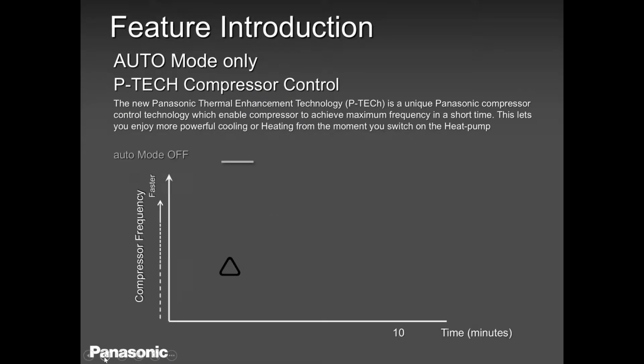Our compressor, we make our own compressors. We have our own factory that builds these compressors, and they build them very strong. I'm telling you very strong because in my 6 years here with Panasonic, I have very rarely seen bad compressors. So how it works? For the first time when you turn it on, don't expect the compressor to run like crazy or the running amps to go up to where they're supposed to be. It's going to take time, guys, more than 3 minutes.